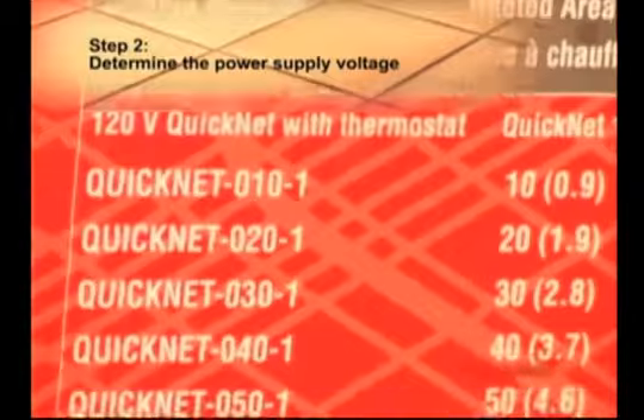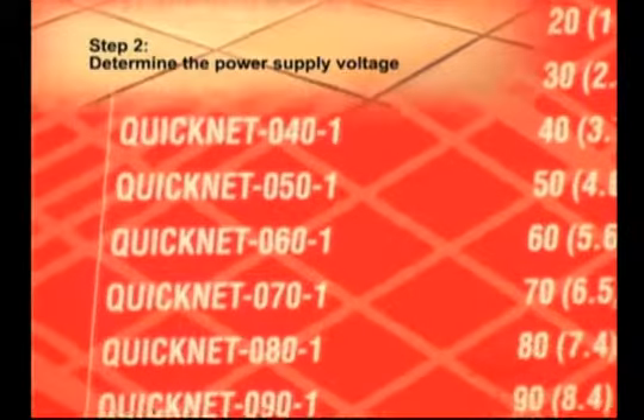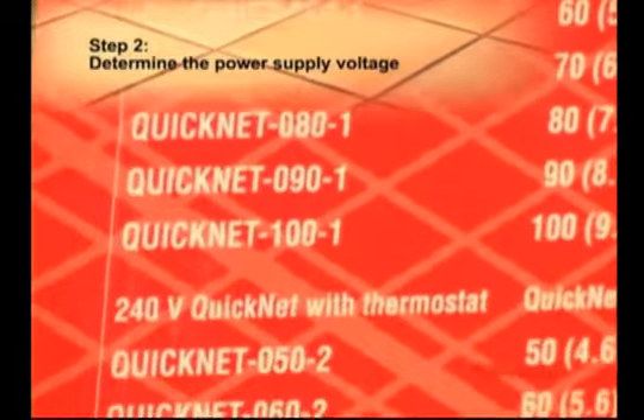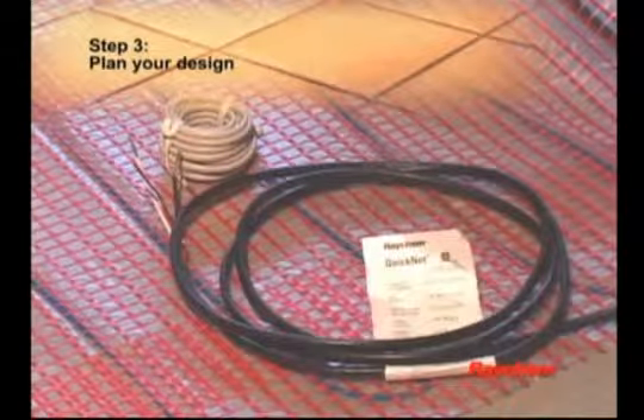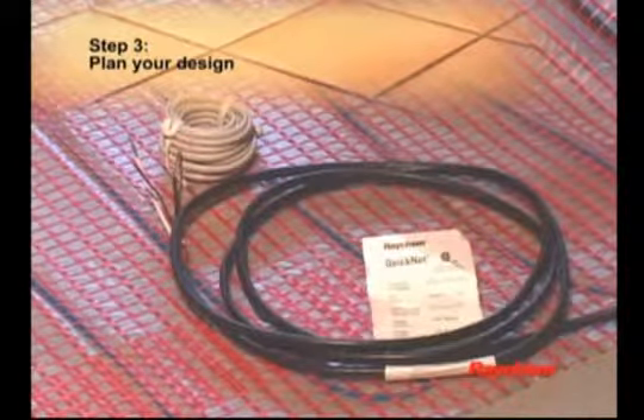square foot mat. The available supply voltages for QuickNet are 120 or 240 volts. Select the appropriate mat for the power being supplied. Select a spot for the thermostat in the wall above the heated area where it can be reached by the 10-foot cold lead on the QuickNet mat and the 10-foot floor temperature sensor.